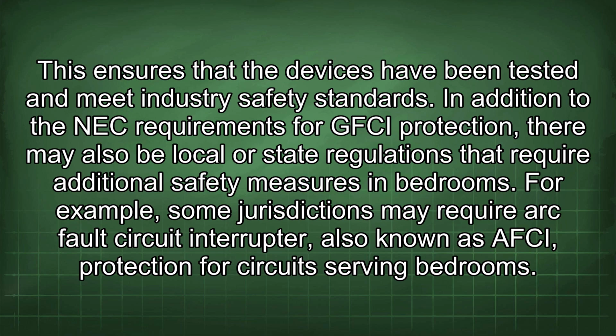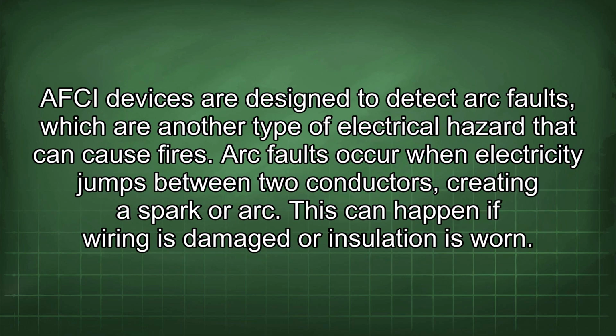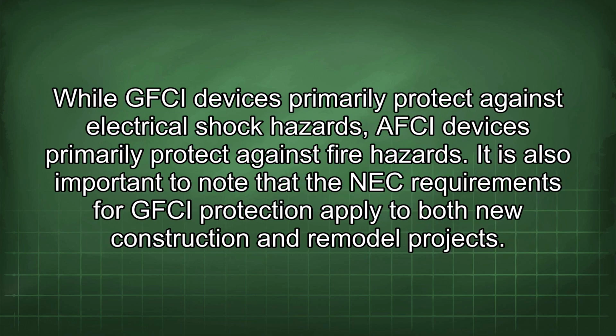In addition to the NEC requirements for GFCI protection, there may also be local or state regulations that require additional safety measures in bedrooms. For example, some jurisdictions may require arc fault circuit interrupter, also known as AFCI, protection for circuits serving bedrooms. AFCI devices are designed to detect arc faults, which are another type of electrical hazard that can cause fires. Arc faults occur when electricity jumps between two conductors, creating a spark or arc. This can happen if wiring is damaged or insulation is worn. While GFCI devices primarily protect against electrical shock hazards, AFCI devices primarily protect against fire hazards.